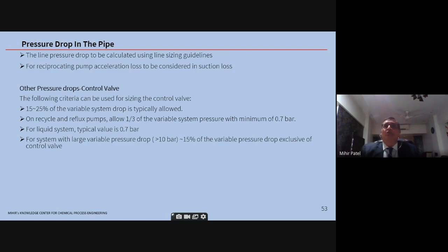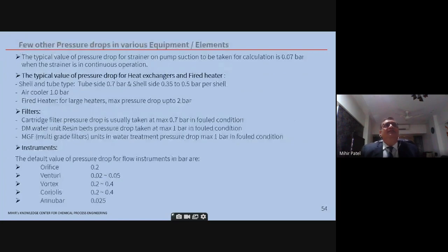If the system needs more pressure drop, then the selected control valve should be able to give up some of the pressure drop by opening up more without compromising on performance. Similarly, if the pressure drop in the system decreases from that designed for, then the control valve should be able to absorb some pressure drop. That's why you need to give some decent delta P to the control valve. If I give 5% of the system drop, that control valve is not going to be able to control properly. So we need to understand this when designing control valves. Then these are some pressure drops I've kept in the slide. For example, a suction strainer on a pump, 0.07 bar.